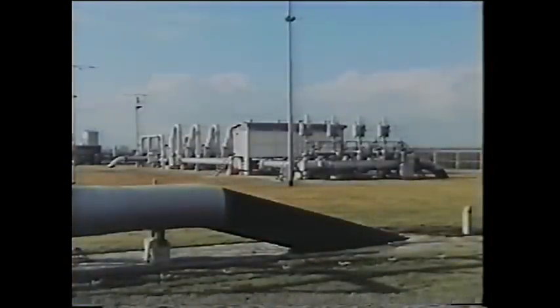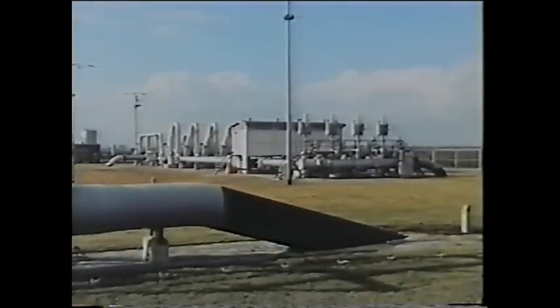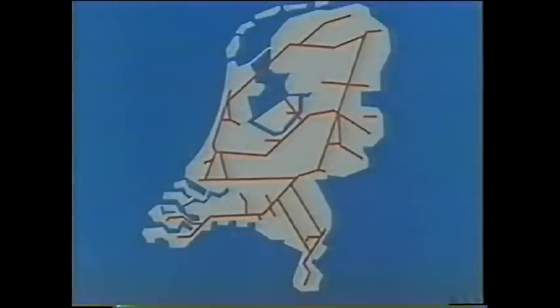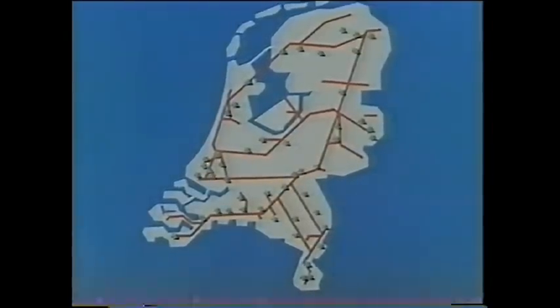This is the beginning of the pipeline network. The dried gas comes in at a pressure of 66 bar. Via the mainline network, the gas is transported all over the Netherlands and to the frontiers. Pressures in this network range from 66 to 45 bar. At over 50 points — the measuring and regulating stations — the pressure is reduced to 40 bar to supply the regional network.